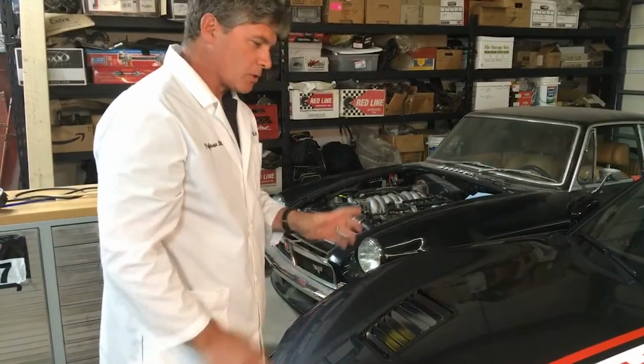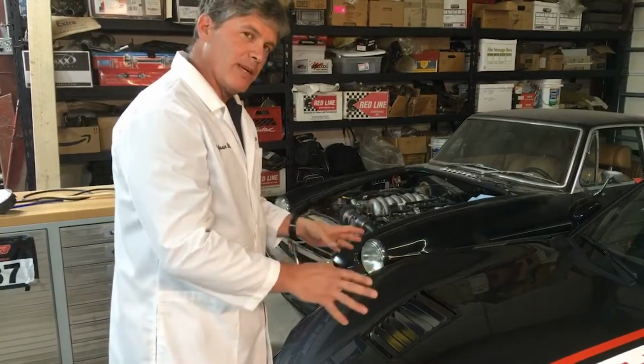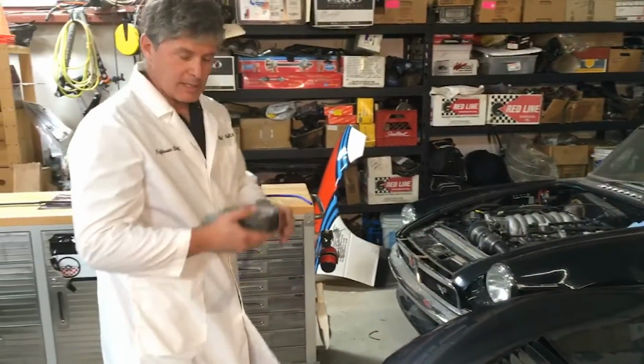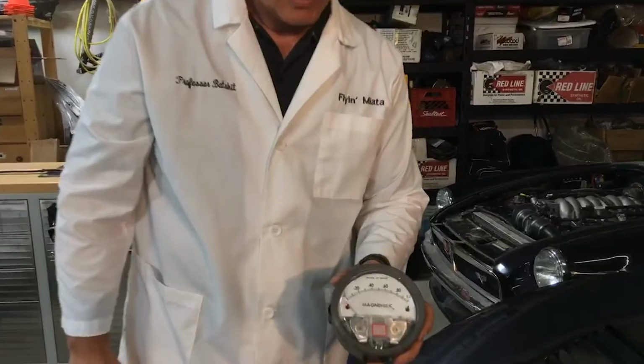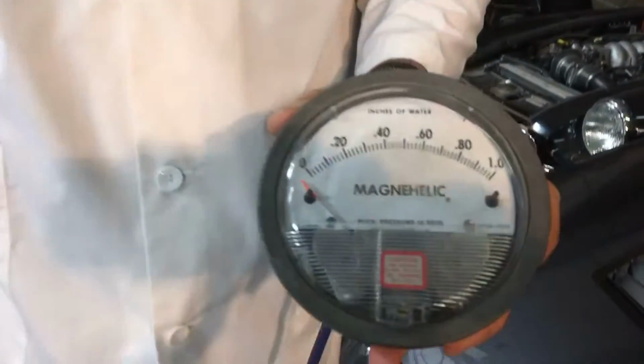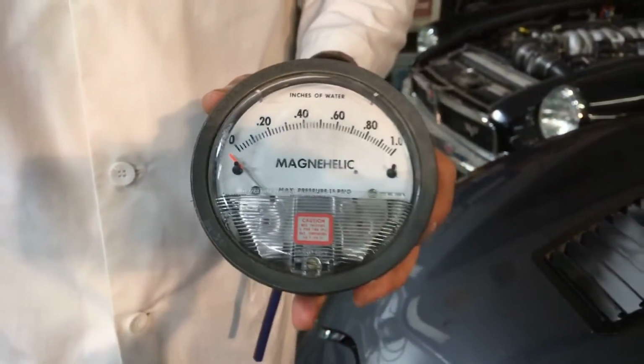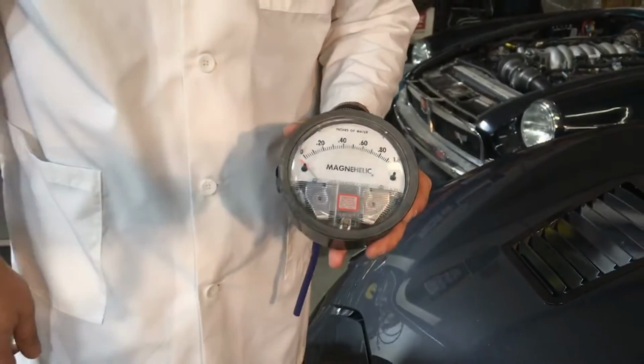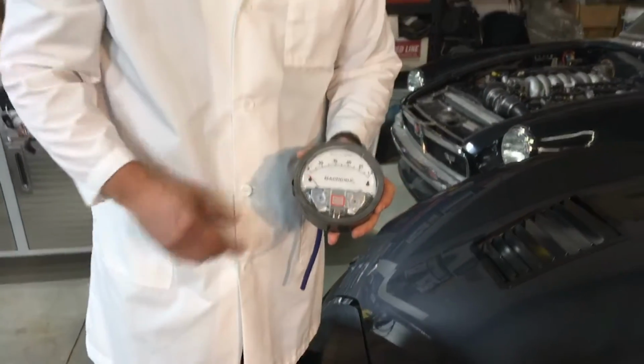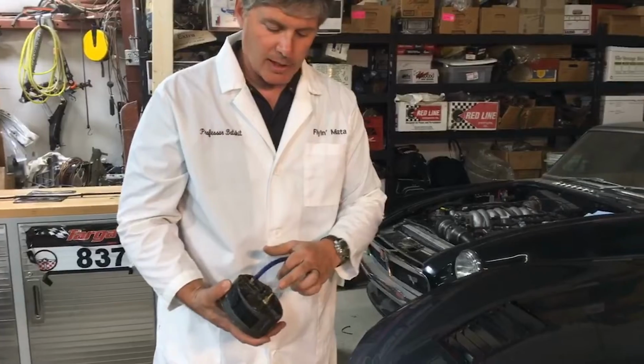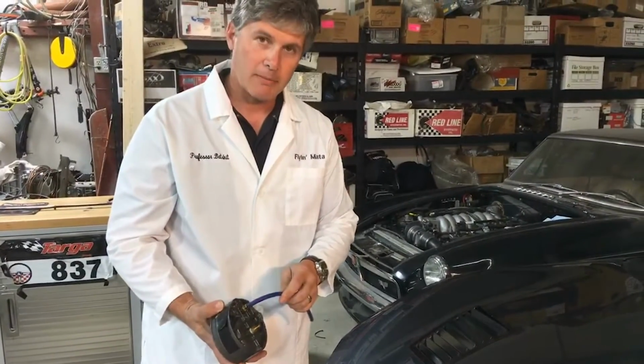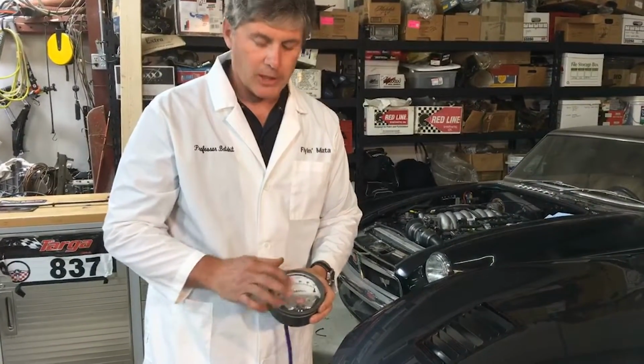But the way that works really, really well for dealing with stuff like hood vents is a magnehelic gauge. This one's been around the block. You can pick these up for $60, $70 on Amazon - I'm sure there are other sources where you can find one used. Basically, it's just a cup that's got a high pressure and a low pressure tap on the back, and it shows you the difference in pressure between those two.